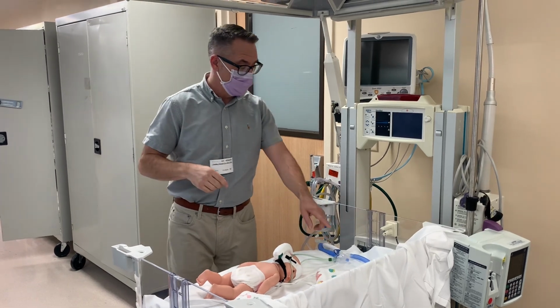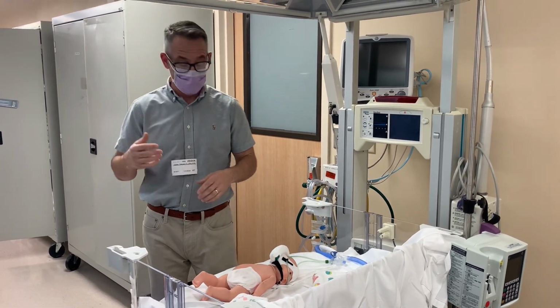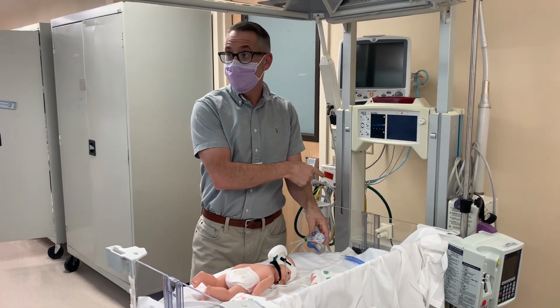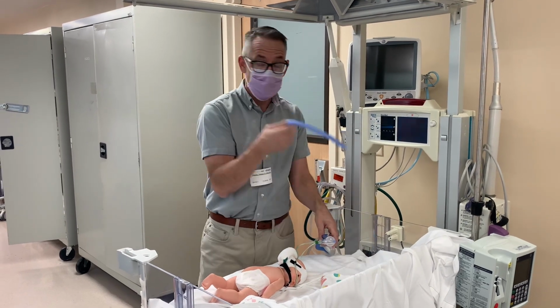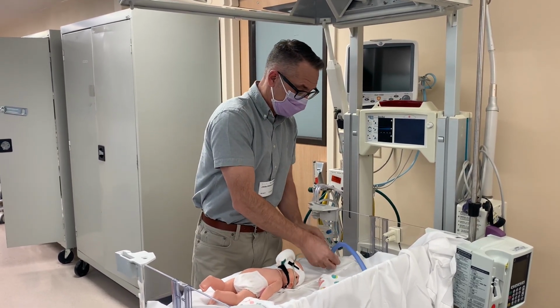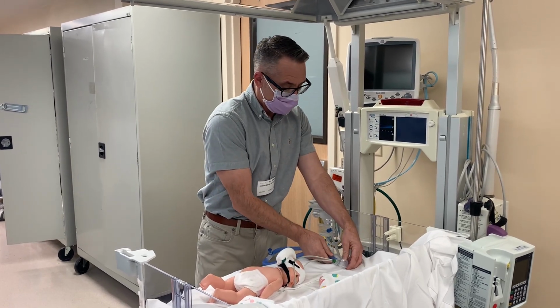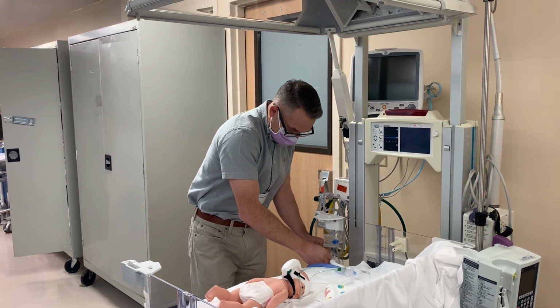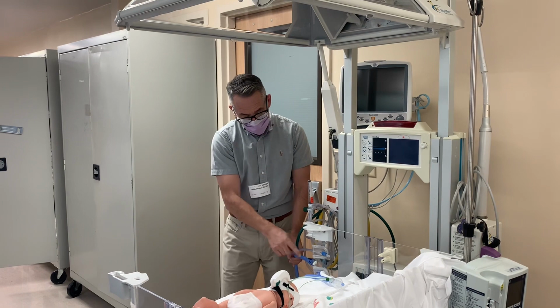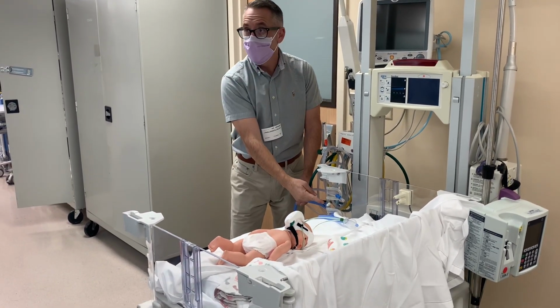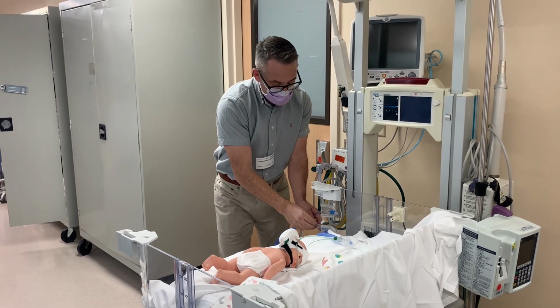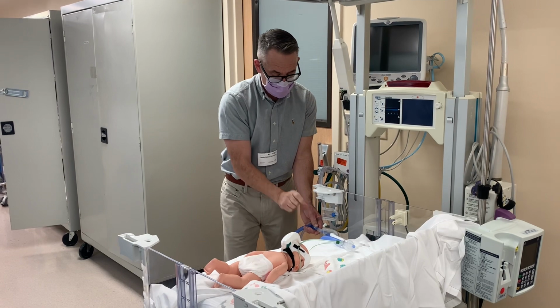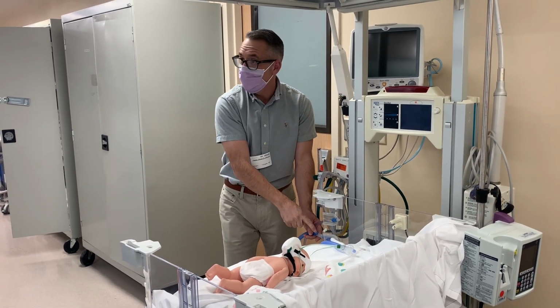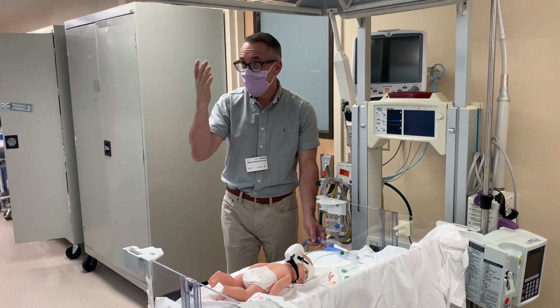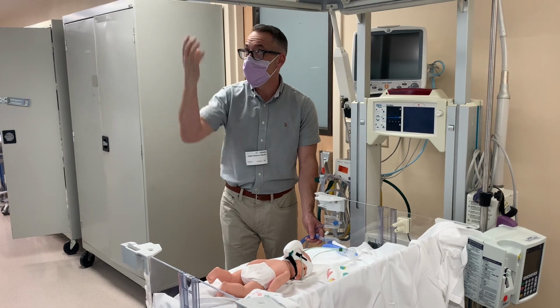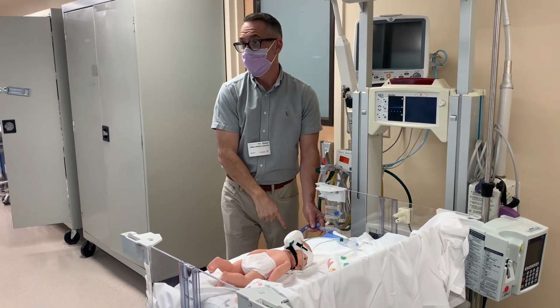Final thing is a question from one of the RTs: what about ambient airflow? Let's say this temperature probe was underneath an air conditioner or a heater, will that cause a haywire? It will, first off, if the temperature probe is outside the incubator and underneath it. So if you insist on using the extension unit, let's create that. If you say I need to use the extension unit because that's just too short for me, whatever your reasoning is, and let's say this is outside like this. Now we've got the temperature probe outside, and let's say an air conditioner or a heater is blowing down on that. That will cause a problem if your temperature probe, that teal color temperature probe, is not seated all the way. If you can see even a little bit of teal sticking out, it's taking an average reading of the air around it. And if it's taking in that air conditioner or that heater, it's going to give a false reading inside that circuitry.